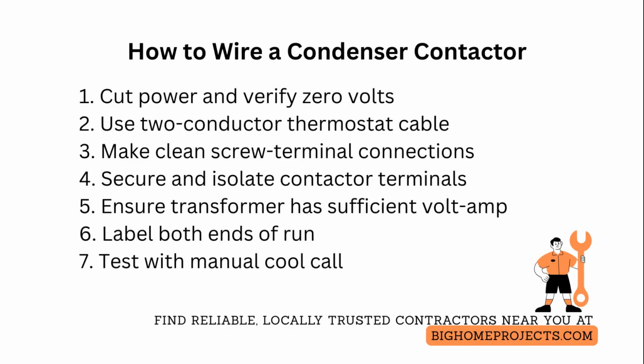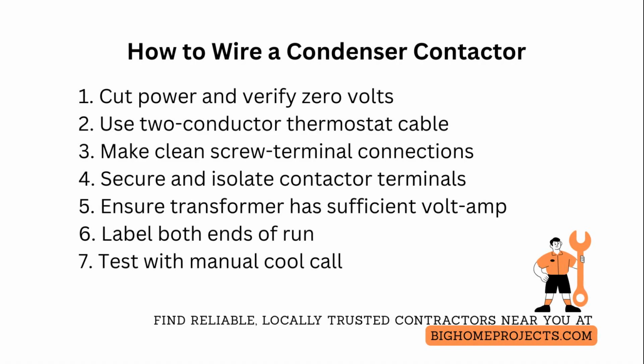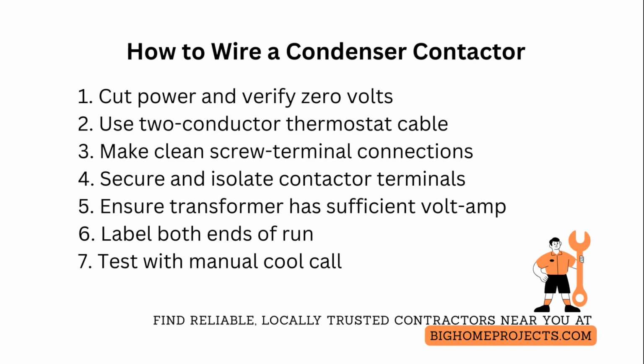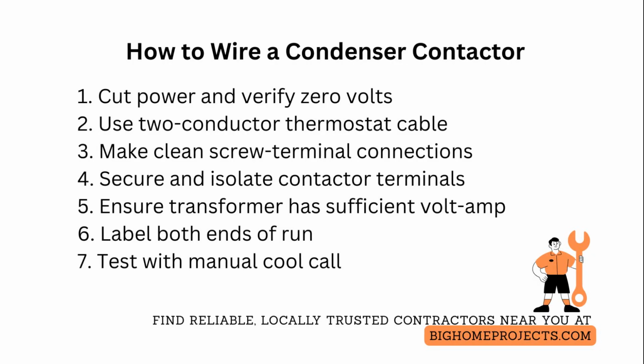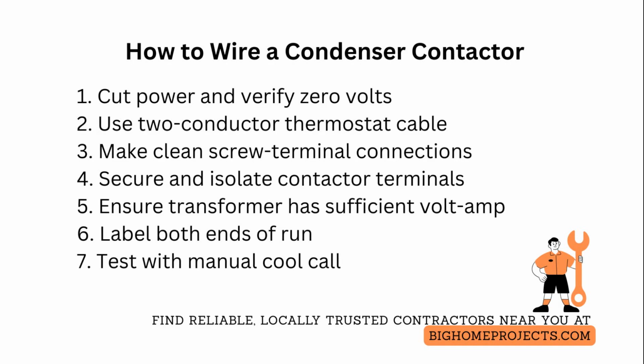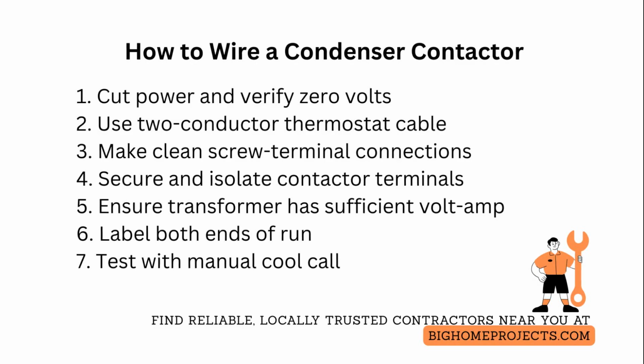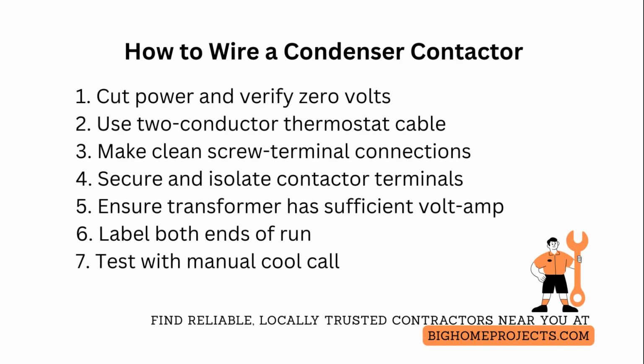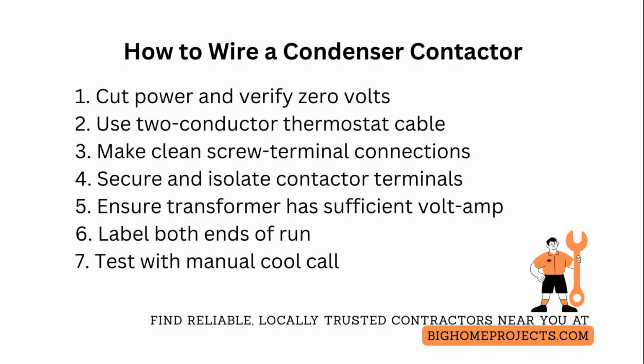Treat the control board terminals marked Y and C as the thermostat load outputs and confirm that Y is energized when cooling is commanded. Use 2-conductor thermostat cable or separate conductors sized per local code. Remove just enough insulation to make clean screw terminal connections and avoid nicking conductors, which leads to high resistance and intermittent operation. At the condenser, land one conductor to the contactor terminal labeled A2 or the coil lead and the other to the opposite coil terminal.